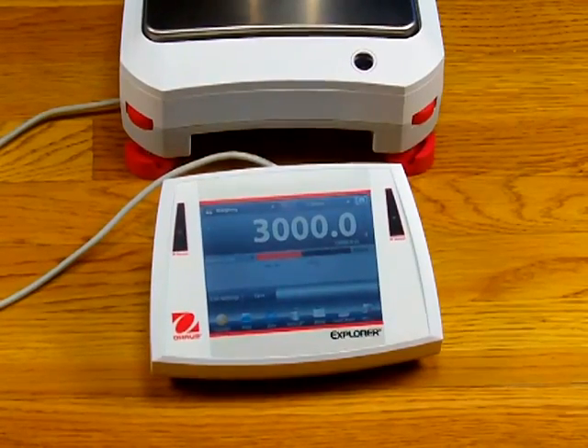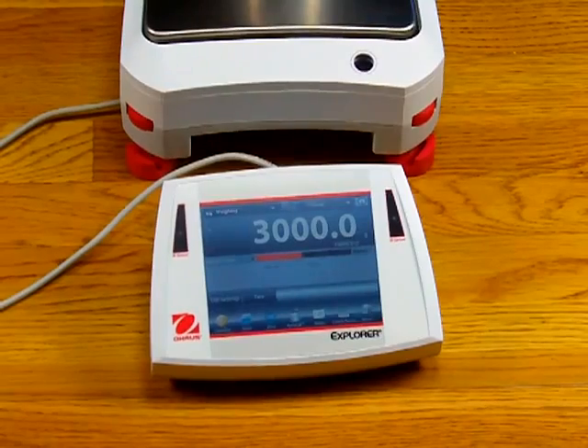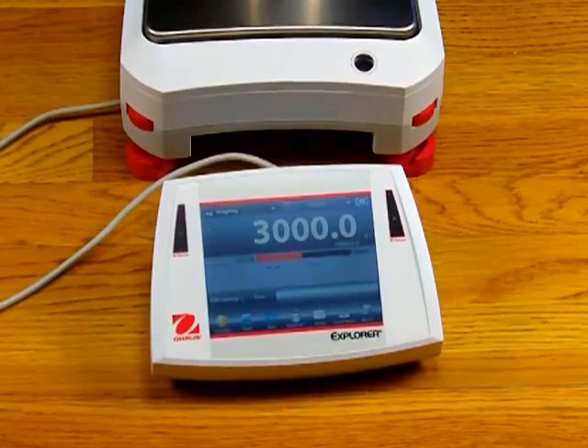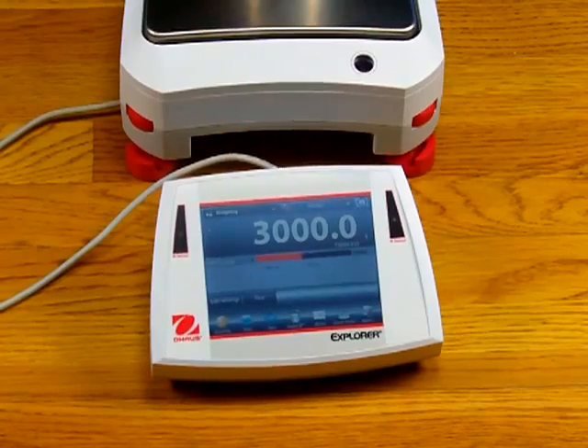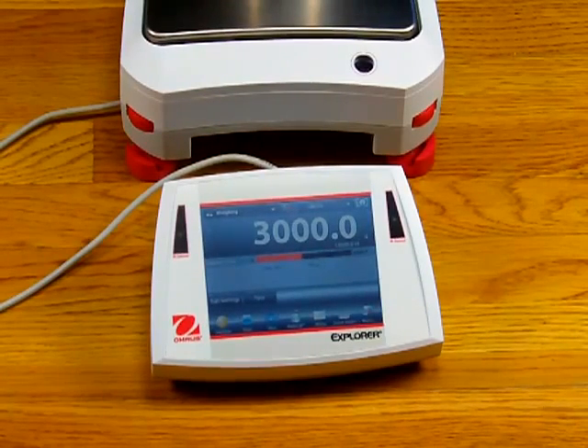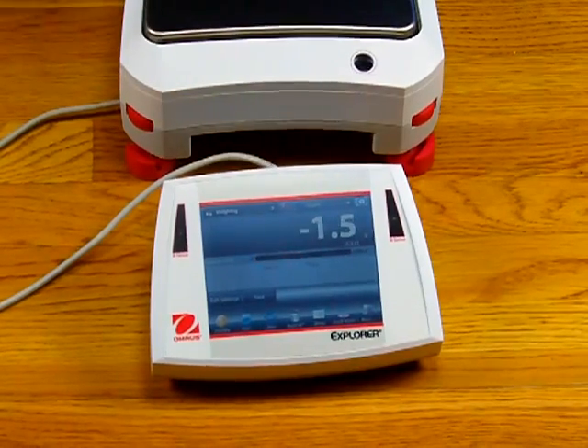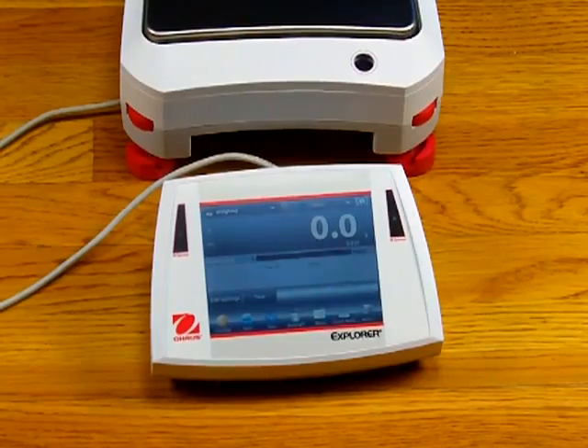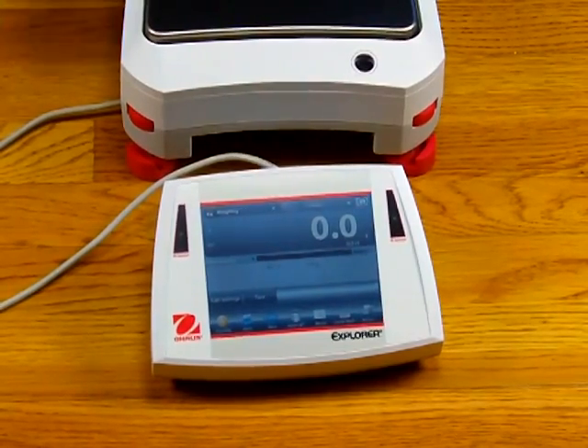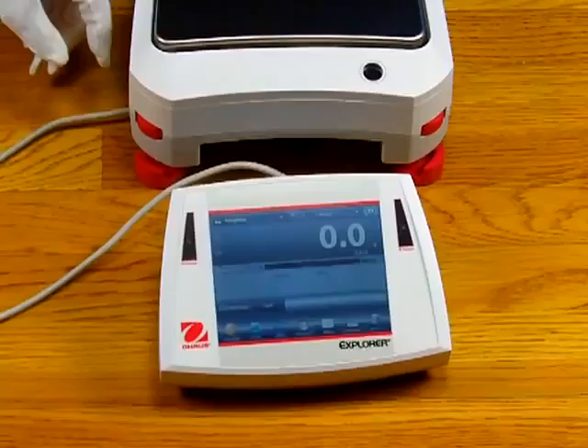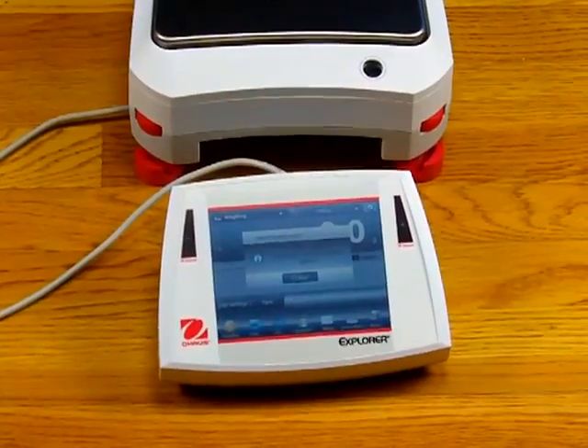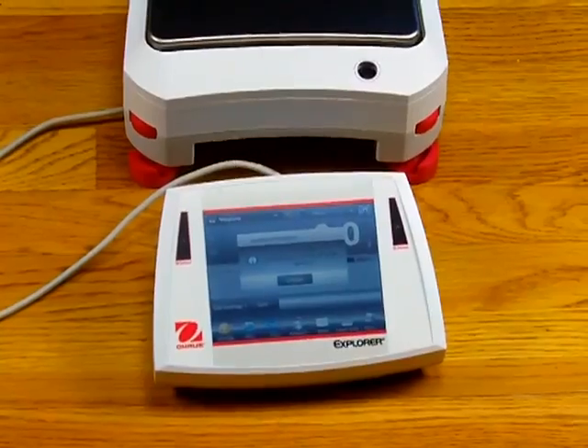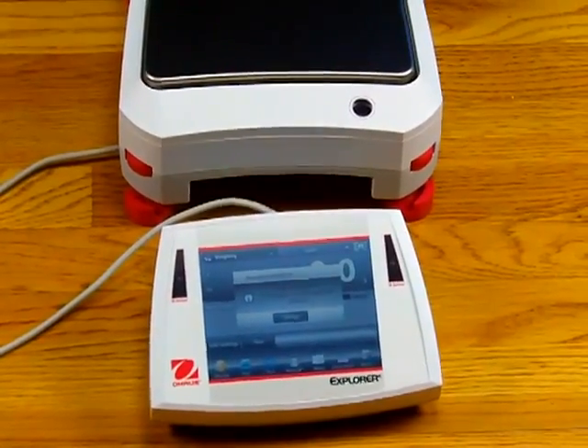The user can specify these settings and also store them in the Ohaus library so you can recall them easily. All of the new Explorer Voyager series has motorized internal calibration, so calibration is simple and fast. I'm just going to wave my hand over the sensor, and as you can hear the motor, the balance performs the calibration.